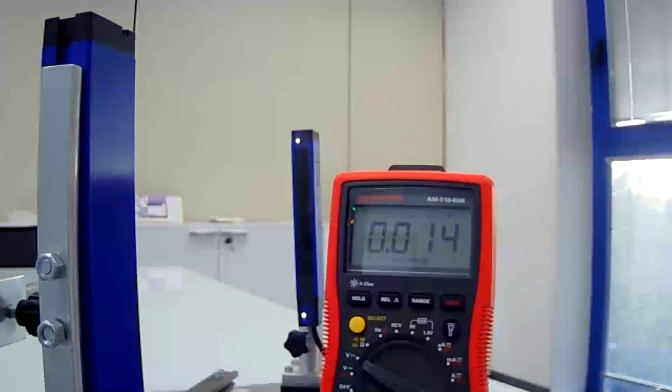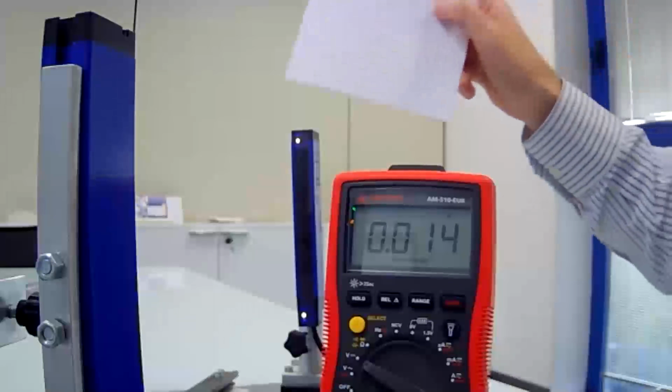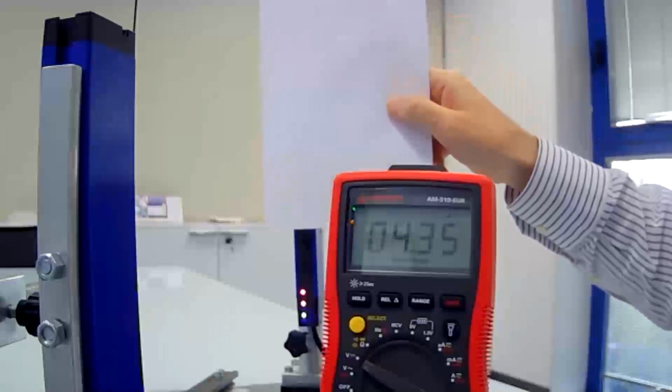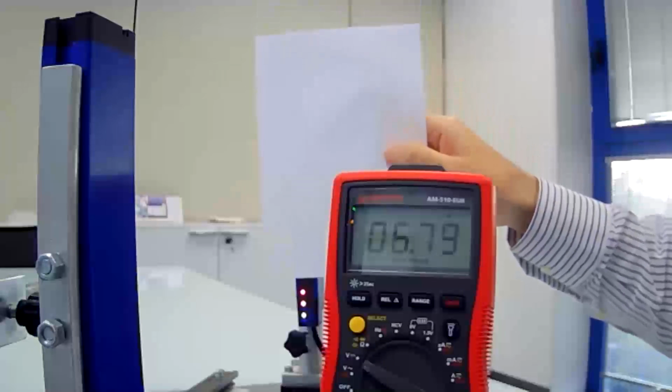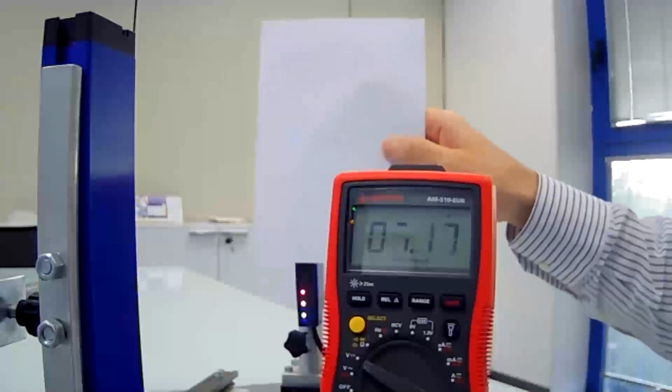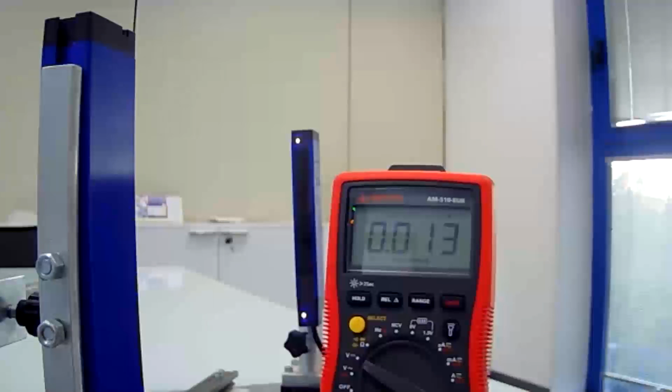While in the previous model, the 6.0 model, we have only the digital output, in this series we also have the possibility to have analog output. So an output that gives us not only information that the target is present, but also how many optics are obscured by the target. We can also work, like in the previous model, in normally open and normally closed.